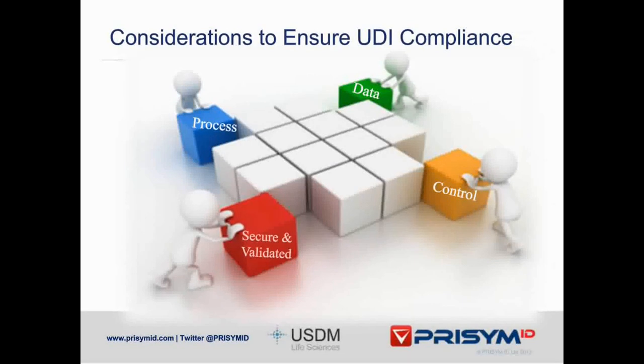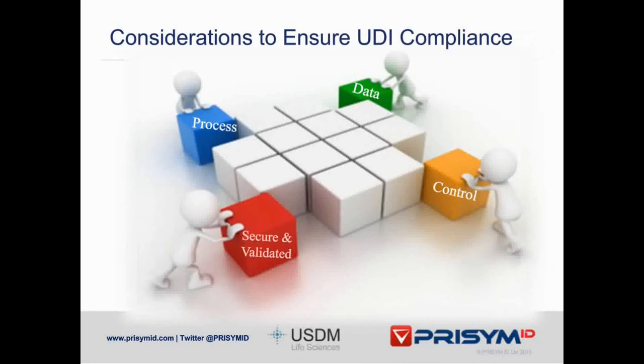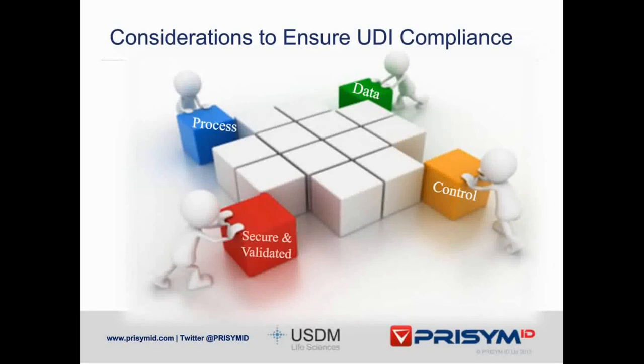There are four things to keep in mind when preparing a strategy to manage labeling lifecycle operations and prepare for UDI. First, ask yourself: is my labeling operation CFR Part 11 compliant? Is your labeling operation validated as a closed, secure environment utilizing electronic records, security protocols, and electronic signatures captured in a single record of truth? CFR Part 11 compliance should be the backbone of any medical device labeling environment. If you cannot capture an action or historical version of a record in your single record of truth, can you prove it occurred — and how quickly could you respond to an FDA auditor?